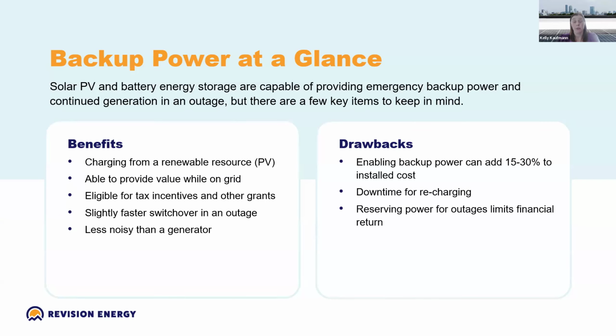But some drawbacks to be aware of: if you're investing in these systems, or have an existing system on site, it's very likely not enabled to work while the grid is down. You have to specifically ask for this. There's extra equipment and software involved in enabling these resources for outage use, for the safety of electrical workers and to make sure we're not feeding electricity back into a grid that's down, which could be very dangerous.